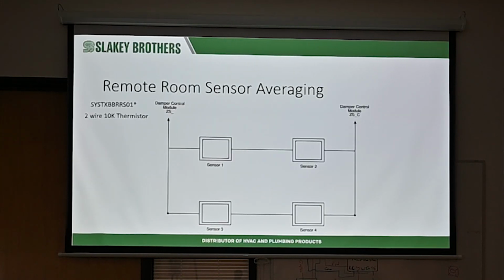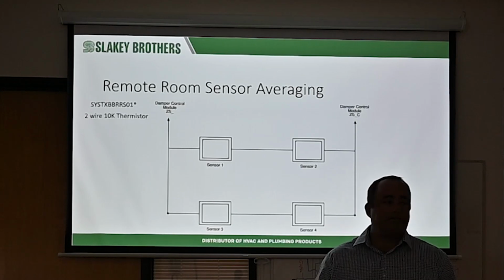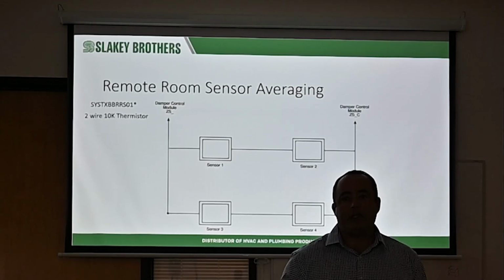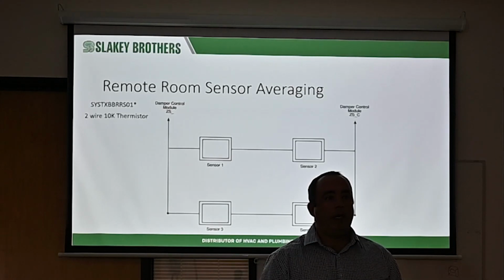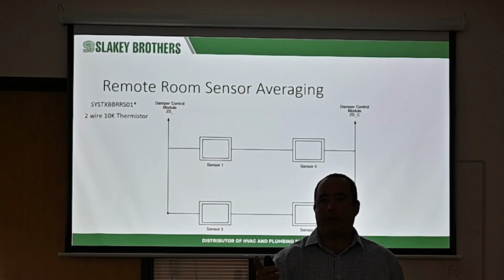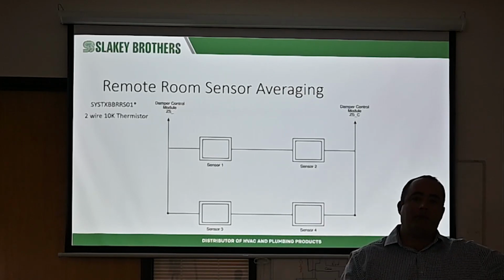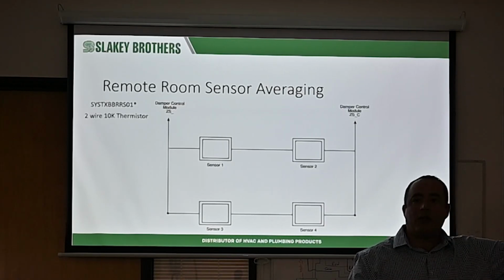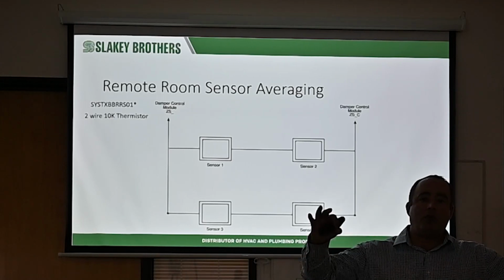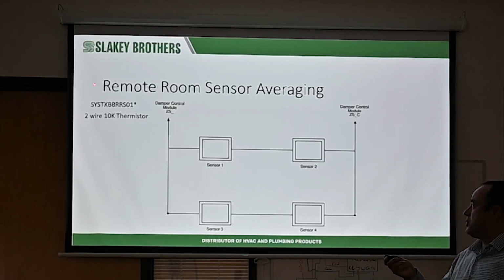Okay. Room sensor averaging, this one is important. You can do this for zone, you can do this for an individual thermostat, and this is where offices, for instance, okay? Let's say you got just one system overall, and you want to try to keep it as even as possible overall. So they're saying it's a little bit too warm because of the sun over there. This area is a little bit cooler, so you want to average out the temperature. You need 4 sensors to do it. So if you're going to do averaging, you have to have 4 sensors overall. So you would put 1 in here, maybe you put 2 in here and 2 in this room, or 1 in each office and then 1 out here.